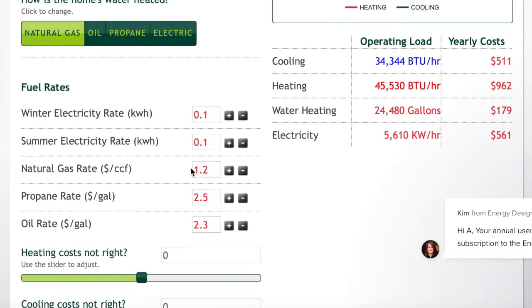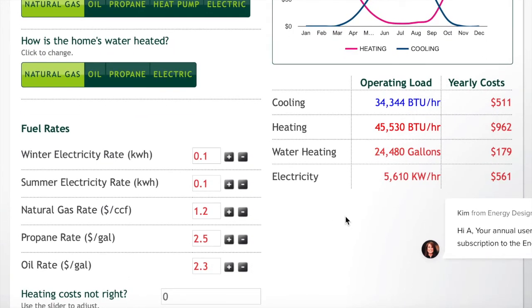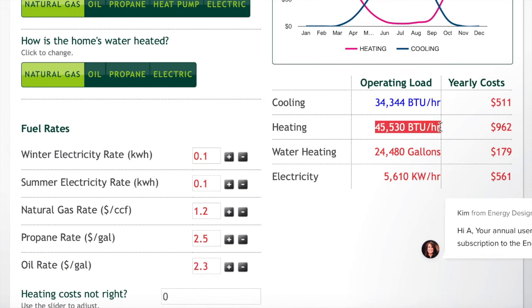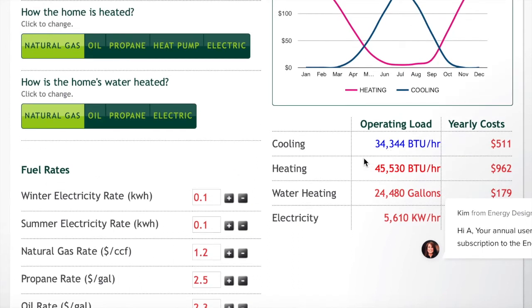Once all that's inputted, the load calculator gives us results. Starting with the heating load: in order to properly satisfy the thermostat year round, we need at least 46,000 BTUs of heat per hour. So we need at least a 46,000 BTU furnace to support the heating load for this property year round.